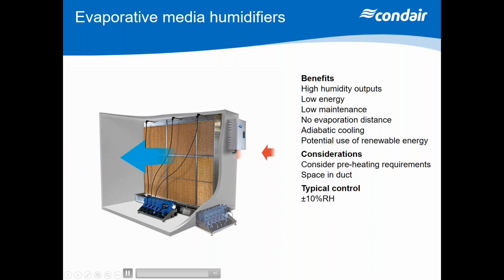You have a tank of water in the bottom there. When we get a demand signal, water is pumped through this hydraulic module, goes up through these tubes, and there's an encapsulated spray bar in the top of the unit that then cascades water over this glass fiber porous material, and then is circulated round and topped up as required. So pretty simple in its operation. We can get high humidity outputs out of these. They start at 30 and they go up to, well, almost 1,000 kilos an hour on really large units.